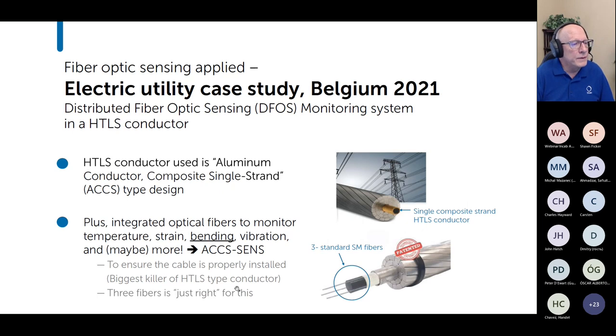The biggest killer of high temperature, low sag type conductors is the fact that they tend to be very bend sensitive. They're very strong in tension, but not so good in compression. And so that means when you bend them, they can break. And if they break, then you've lost that strength and therefore you've lost the benefit of the whole design concept. So what causes them to get bent too much? Well, installation is arguably the leading killer of these types of cable: improper installation. So it's very beneficial for utilities to be able to monitor the bending during installation in particular. But in addition, if you're using fiber optic sensing, you can also know the temperature, the strain, and any vibration that's going on during installation. And so then post-installation, you're able to know that the cable was installed correctly, and therefore you're actually going to get all of the benefits of the design concept.